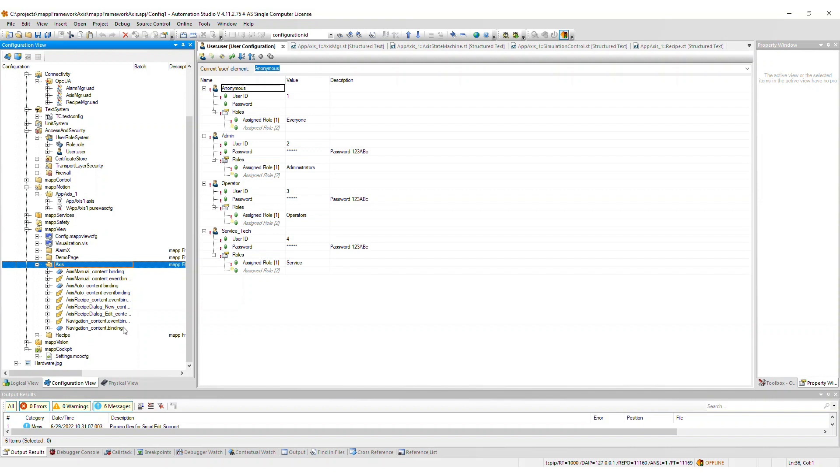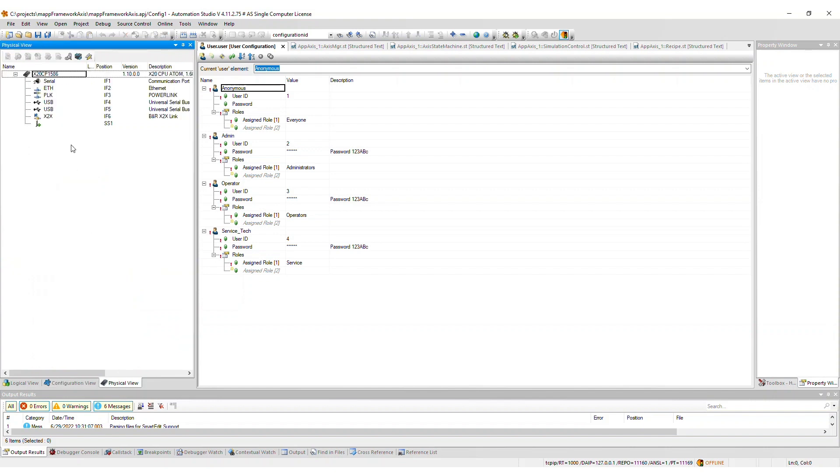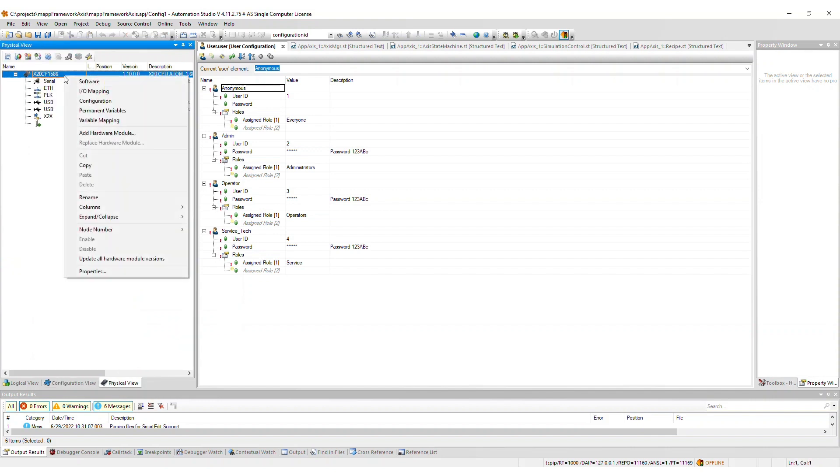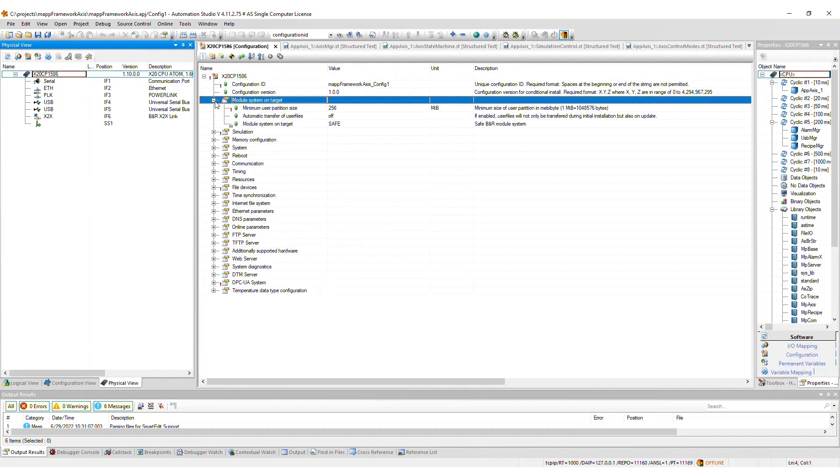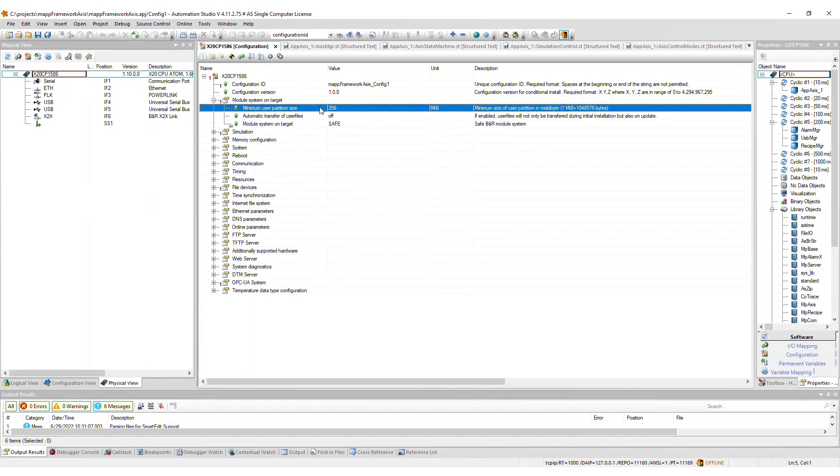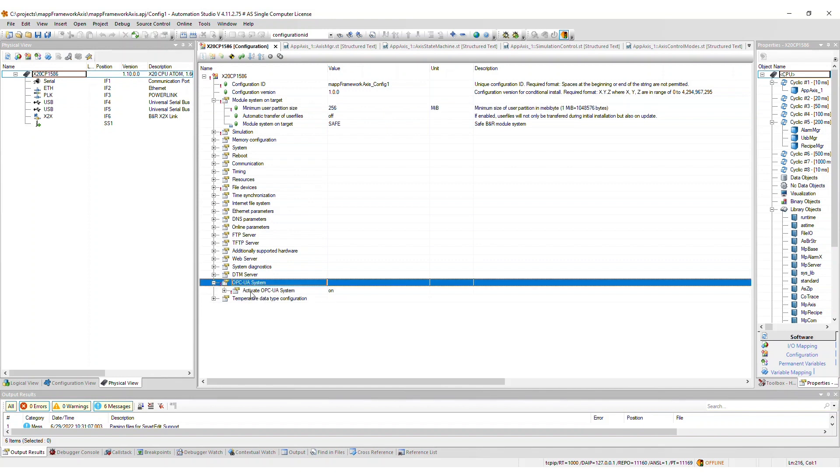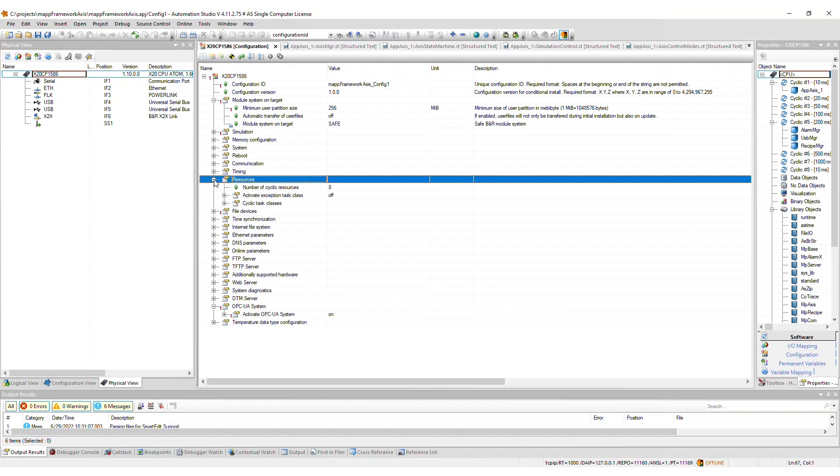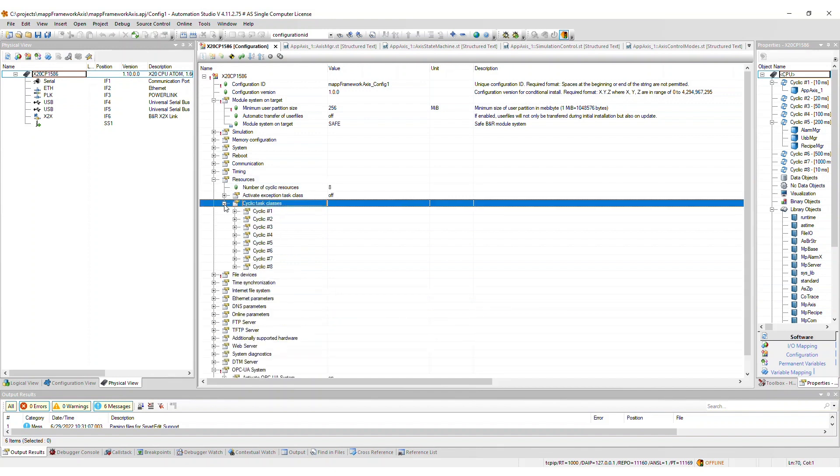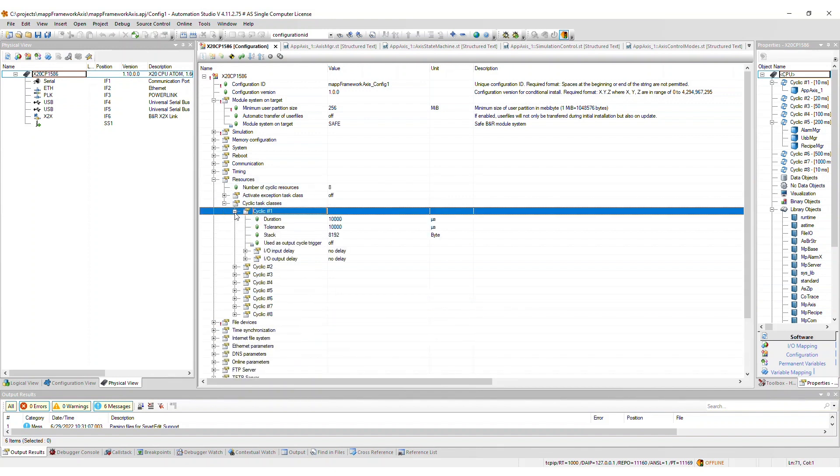Lastly, in the CPU configuration, a few things are changed as well. If your user partition is less than 256 MB, the value is increased as such. If OPCUA is not yet enabled, this will be enabled for you as this is required for MapCockpit. After importing the Axis framework, take care that your task class 1 cycle time is 20 milliseconds or less.